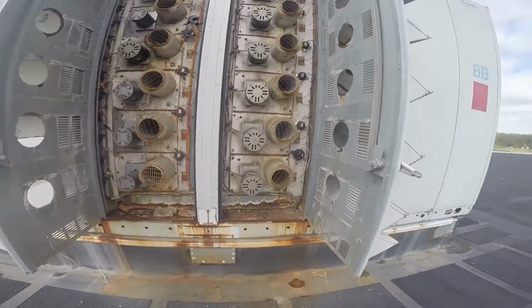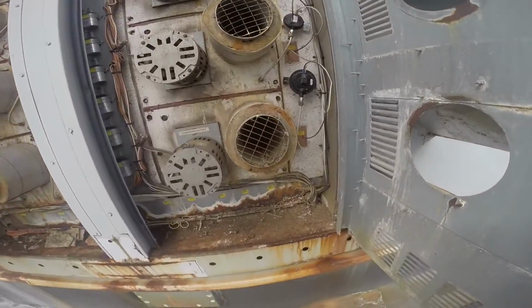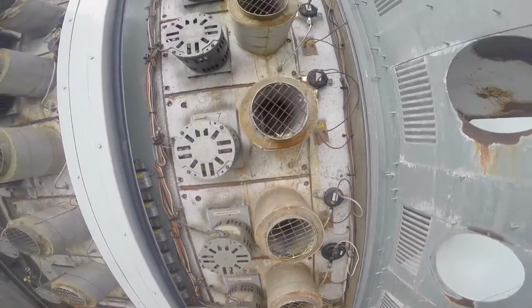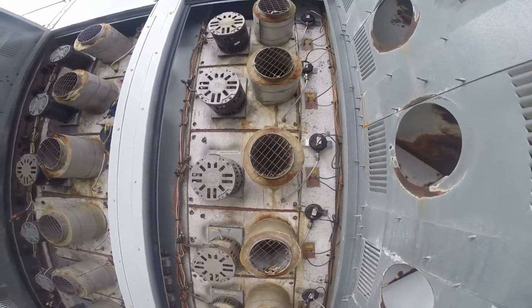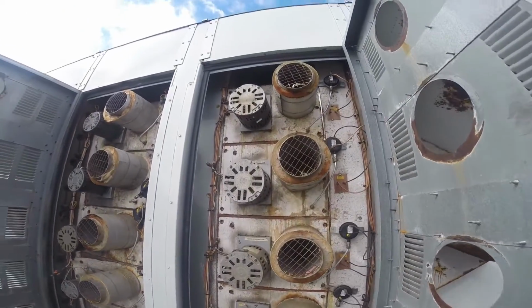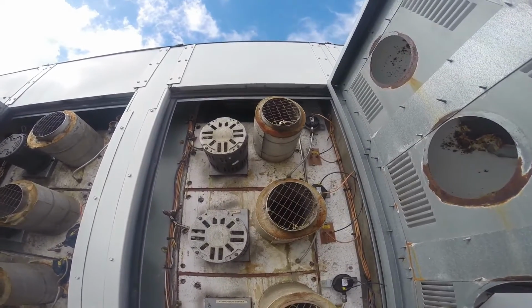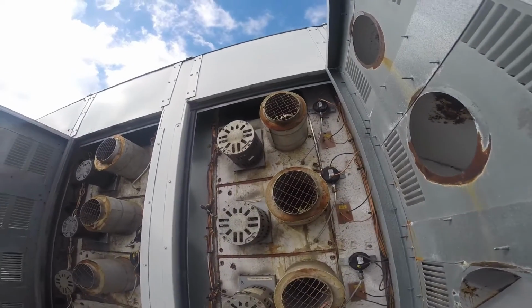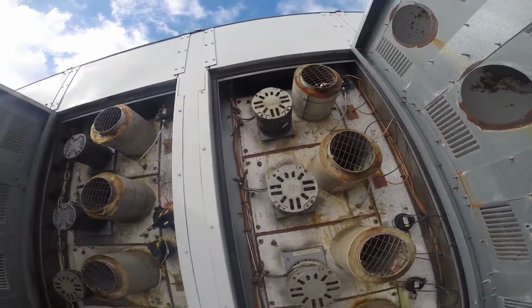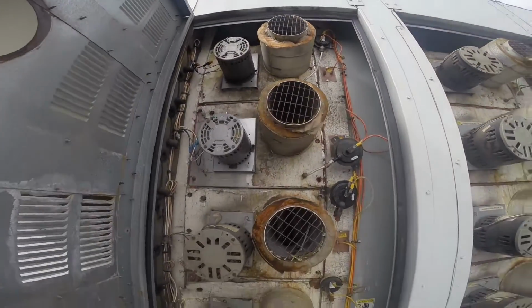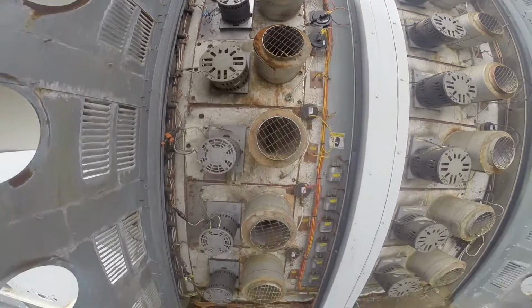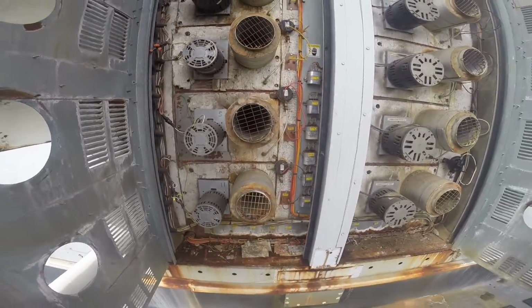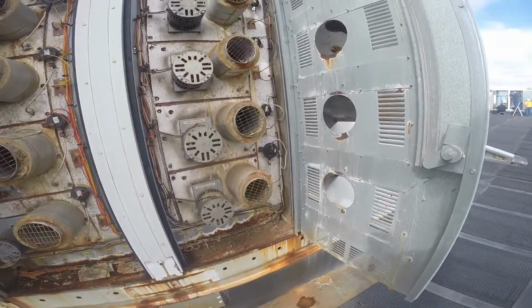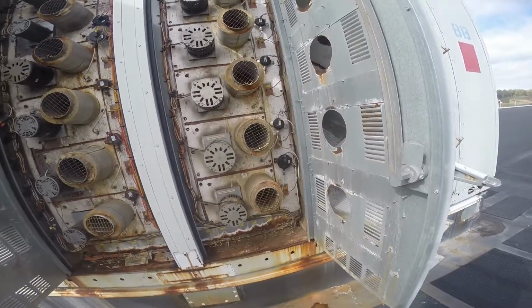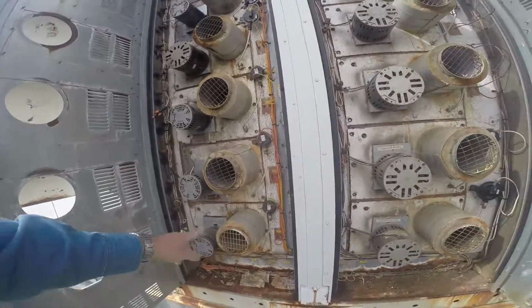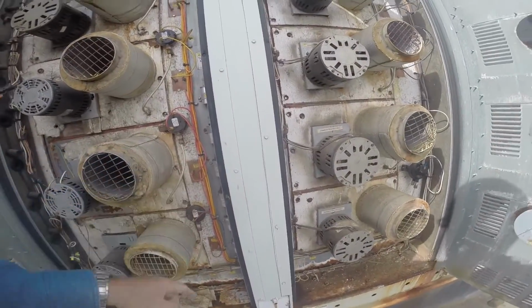As you can see, I'll get closer there. There seems to be quite a bit of debris and dirt on the outlet side of these burners. You look up there, you can see something's broke loose inside. Looks like possibly a piece of caulk or something that's come through the burner section. They've had issues with pressure switches, and they've been changed since the factory. These have been turned up to keep water from running into them.